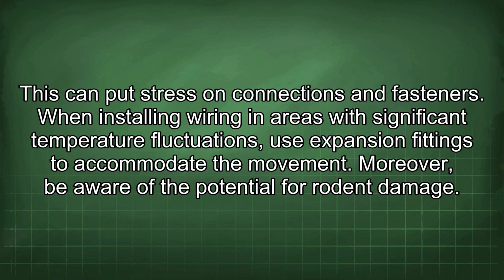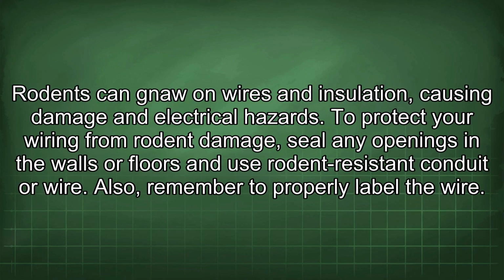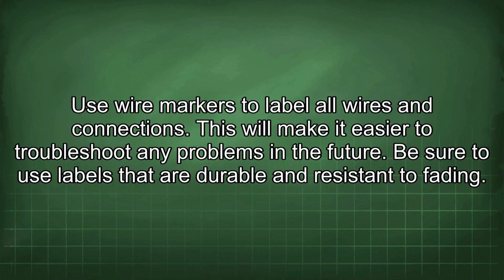Moreover, be aware of the potential for rodent damage. Rodents can gnaw on wires and insulation, causing damage and electrical hazards. To protect your wiring from rodent damage, seal any openings in the walls or floors and use rodent-resistant conduit or wire. Also, remember to properly label the wire. Use wire markers to label all wires and connections. This will make it easier to troubleshoot any problems in the future. Be sure to use labels that are durable and resistant to fading.